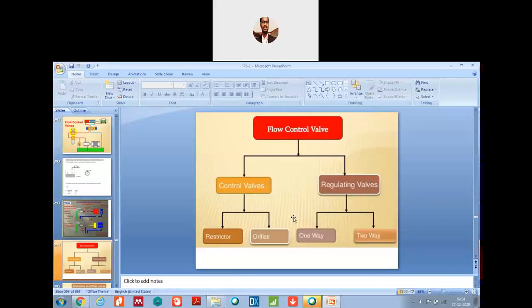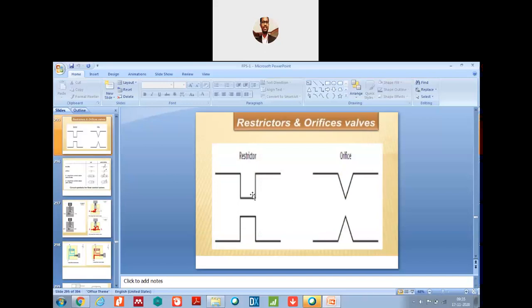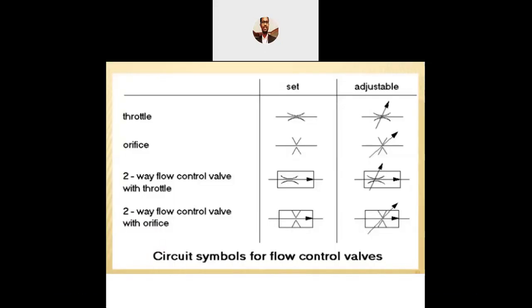How are flow control valves classified? They are classified into control valves and regulating valves. Control valves are of the restrictor type and orifice type. Regulating valves are classified into one-way and two-way types. A restrictor will have a plain flow profile whereas an orifice type will have notches or sections. In graphical representation, a throttle is set and indicated with a fixed symbol; if it is adjustable, it is shown with a cross arrow. Orifice is always denoted with a V-shape. An adjustable two-way flow control valve with orifice is represented as shown.